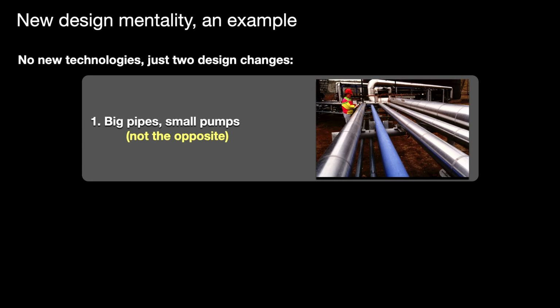But that's wrong, even though it's in all the textbooks. It's wrong because it leaves out the capital cost of the pumping equipment. A pumping system's pump, motor, inverters, and electricals must all be big enough to overcome the friction, so their size, and roughly their capex, will fall as nearly the fifth power of pipe diameter, yet the capital cost of the fatter pipe rises as only about the second power of diameter.